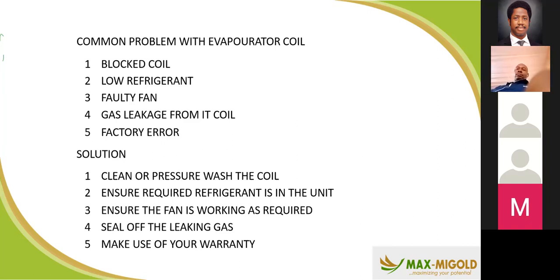Then a faulty fan, gas leakage from the coil, then factory error. Sometimes some of your units come with factory error. Once they come with factory error, if they are under warranty, they can be replaced. And the solution: clean or pressure wash the coil. Just like your car radiator, once it is blocked, what do you do? You pressure wash it to give maximum cleaning. The essence of the radiator is to take cool air from the environment. Ensure your fan is working efficiently, and ensure the required refrigerant is in the unit.